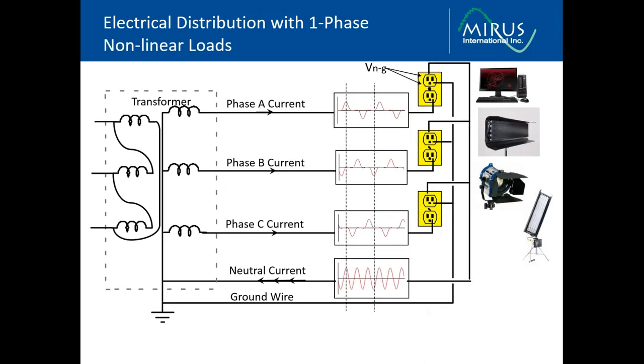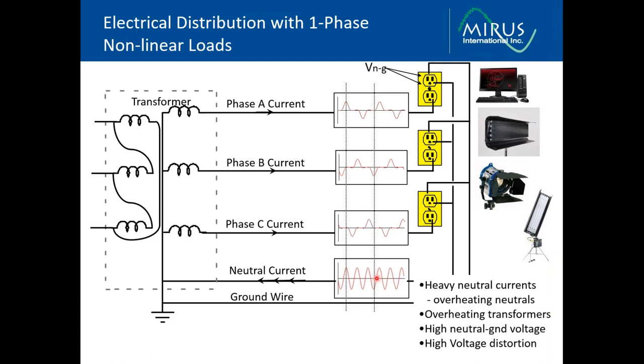But with nonlinear loads, such as many lighting loads, computer systems, and new LED lighting systems, they will draw current in pulses. These pulses are still phase shifted 120 degrees, but now when they combine in the neutral, the pulses are additive. So you can see here there's a pulse on A, but there's no current on B to cancel with it, no current on C to cancel it, so we get a pulse back on the neutral. And this happens all the way across the waveform. Now what we have is, where here we have one period, we have one, two, three periods, so the third harmonic is the predominant current returning in the neutral. So we end up with heavy neutral currents, overheating transformers, high neutral to ground voltage, and high voltage distortion.